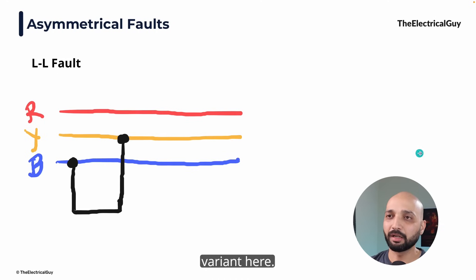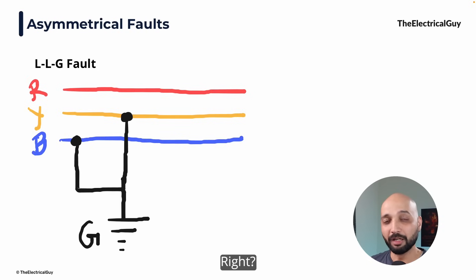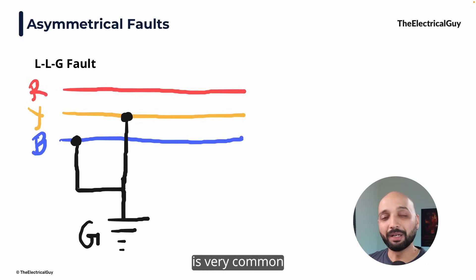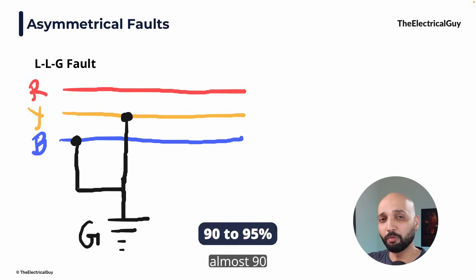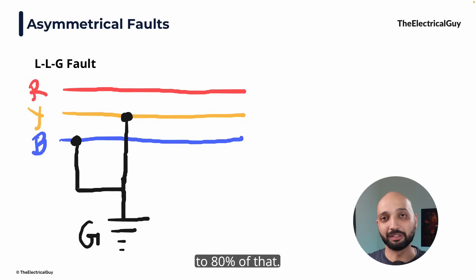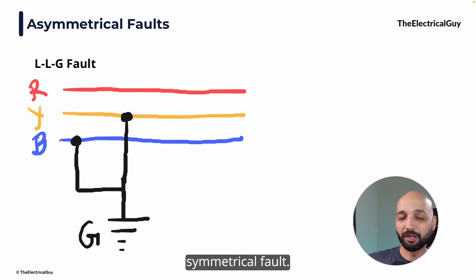There is another variant: the double line to ground fault. In this case, two phases are getting connected to each other and also getting connected to the ground. The occurrence of asymmetrical faults is very common — almost 90 to 95% of the faults seen in the power system are asymmetrical in nature, contributed majorly by the line to ground fault, which accounts for almost 70 to 80% of those. These asymmetrical faults are not as severe as the symmetrical fault we are going to see next.